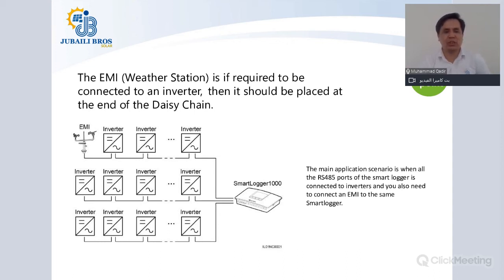The main application scenario is when all the RS485 ports of the smart logger are connected to inverters, and you also need to connect an EMI to the same smart logger. In such a scenario, since you do not have a COM port available, all being used by inverters, you can connect the EMI at the end of the daisy chain.